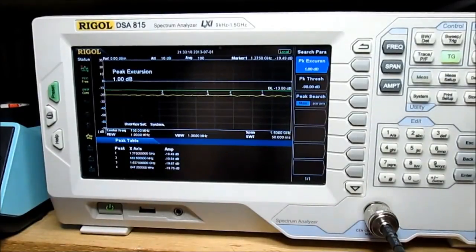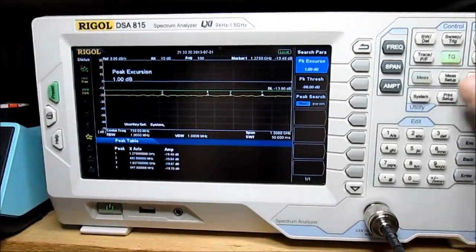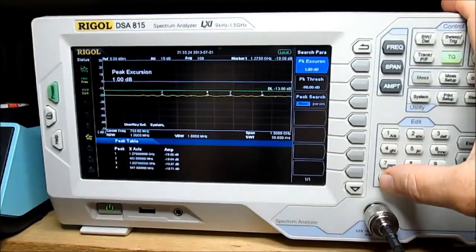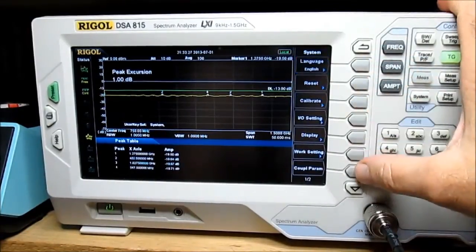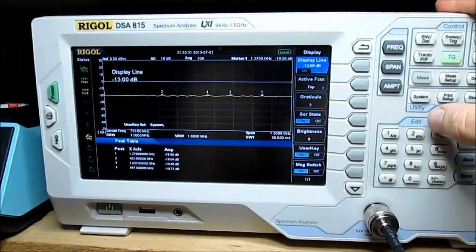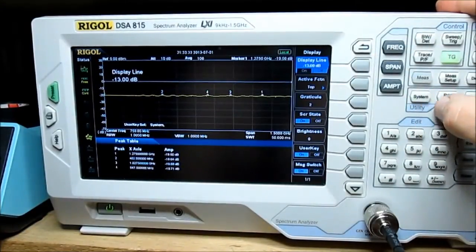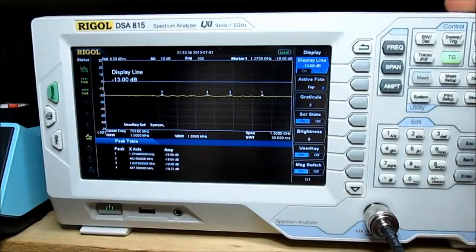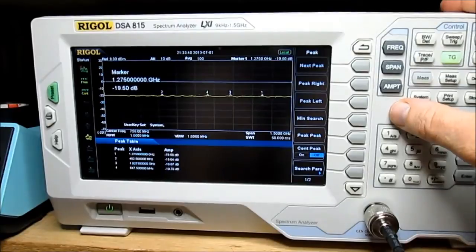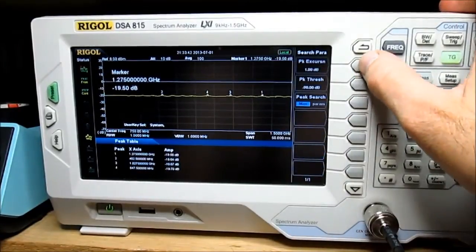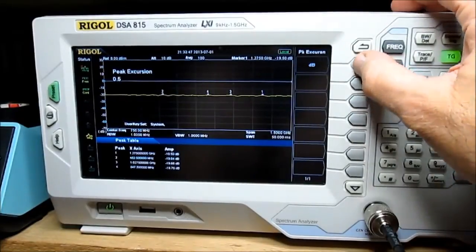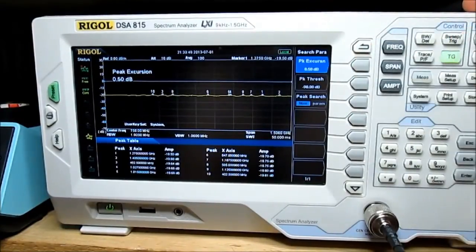See part of the problem is the actual peaks that are there are so small that it really is hard to discern them with the scope. Let me hit system really quick here and turn the display line off. Go back to peak, search parameters, and let's just change this to like 0.5 dB. There we go, a little more there.